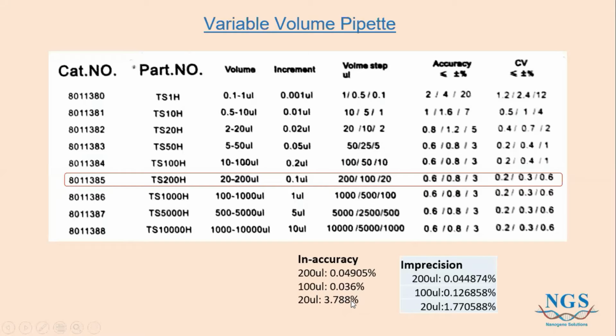So let's just leave it there, and let's look at the imprecision. So I'll give you guys 10 seconds to look at the imprecision, my value, my calculation, and then you can compare it to the table above. And if you could, point out which testing volume is actually incorrect. I mean, it's actually out of the range. So yeah, like I think most of you have already figured out, it's actually the smallest volume that is out of the range. So what does that mean?